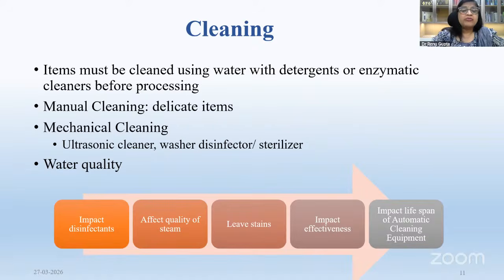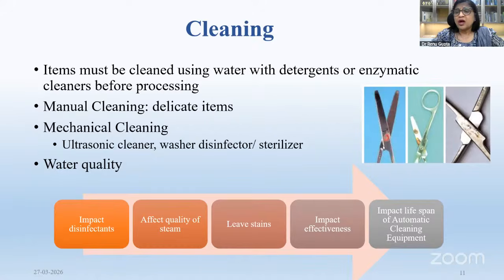And for mechanical cleaners, we have the ultrasonic cleaner. There is a defined cycle. The manufacturer tells you what should be the time of contact, how to put the load, and how water quality is also very, very important because most of the sterilizer processes depend upon water quality. If water is not good, it will cause corrosion of your instrument. It will leave some stains and the life of these instruments like ultrasonic cleaners also deteriorates. Fine. So this is how cleaning has to be done properly and it should remove all the residual matter.